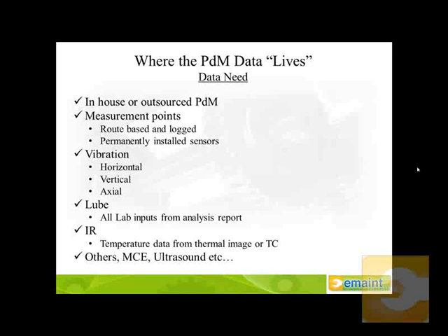And this is where we're talking about the possibility of raw data versus the report format. In a report format, you're going to be given an image or see an image that has a specific temperature associated with an area or a point on there. That could be manually entered. If you have in-house thermal software, you also have the capability of getting the raw pixel data from each one of the images themselves. And then, of course, the other types of data would determine what you're looking for from your motor circuit analysis or ultrasonics. In the case of ultrasonics, you'd be interested in recording the dB levels within your CMMS system.